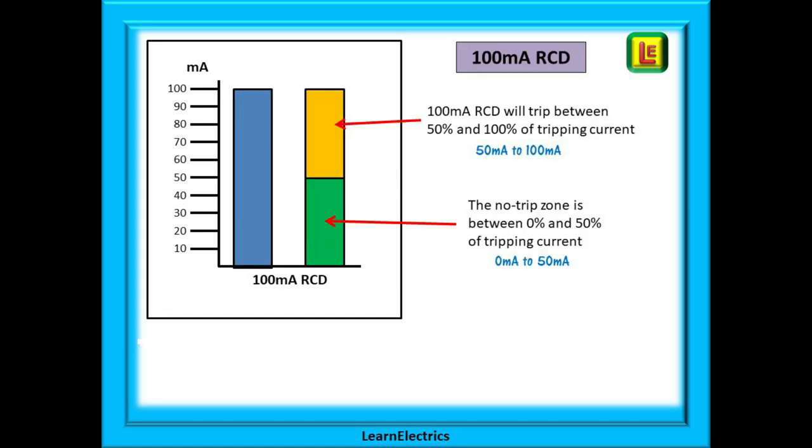Transferring the same logic to a 100 milliamp RCD this will operate at or before 100 milliamps of residual current. This means anywhere between 50 milliamps and 100 milliamps as shown here and between 0 and 50 milliamps is the no trip zone.